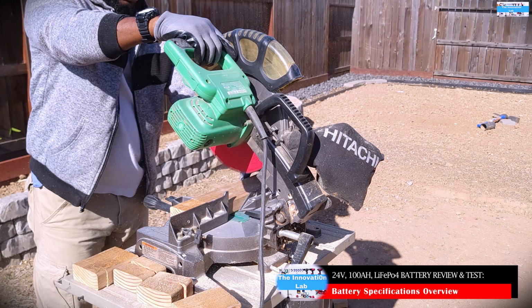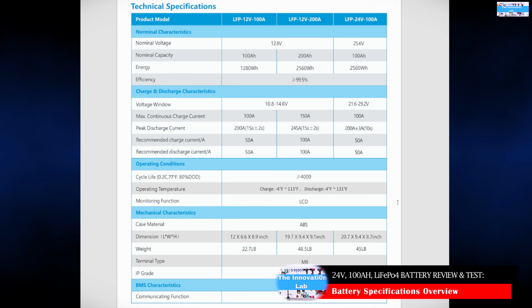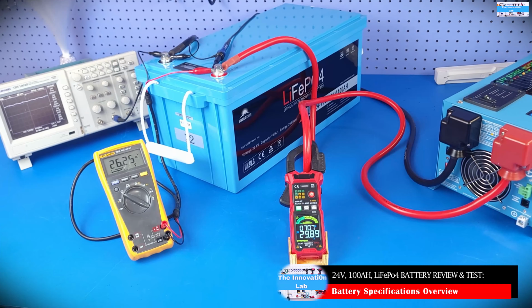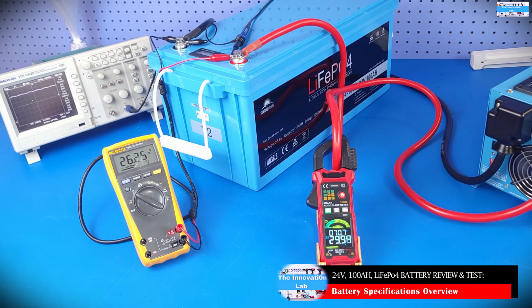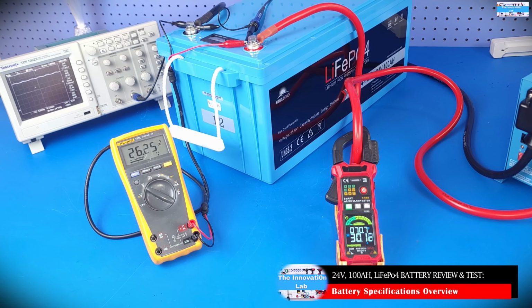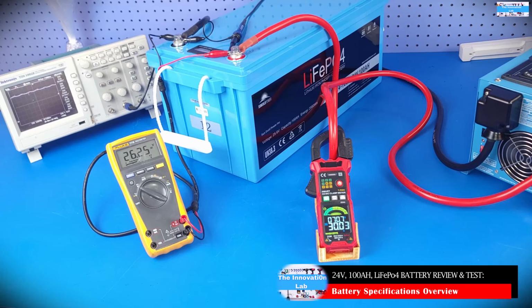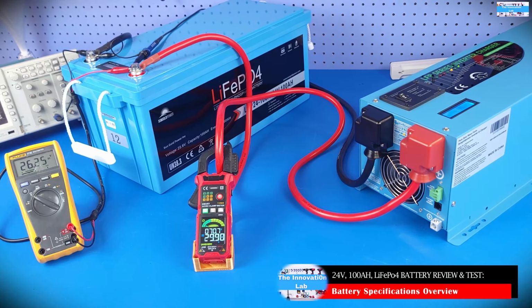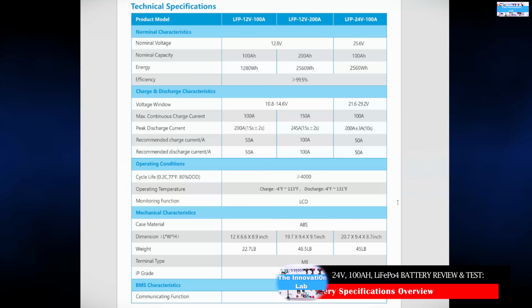However, the recommended charge current for the battery system is right around 50 amps, and if you do the math, this is about 0.5 C. And as you guys know, C essentially represents the nominal capacity of the battery in ampere hours, which is 100 ampere hours. So the recommended discharge current is also 0.5 C, which is 50 amps.